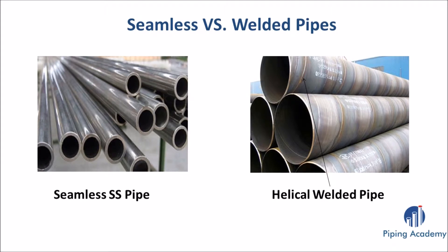The very first question that should come to your mind is whether a welded or a seamless pipe is required. It makes a very big difference in terms of, for example, pressure rating or maximum heat a pipe is able to endure. However, if both welded or seamless production is accepted, it's better to choose a welded execution, because a welded pipe can always be sourced much cheaper and the manufacturing process will be much faster compared to making seamless pipes.